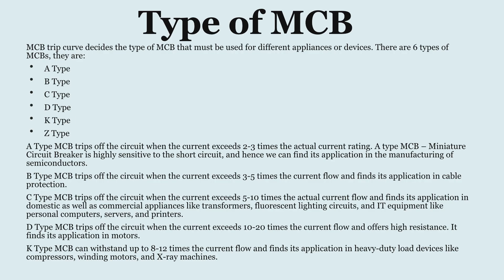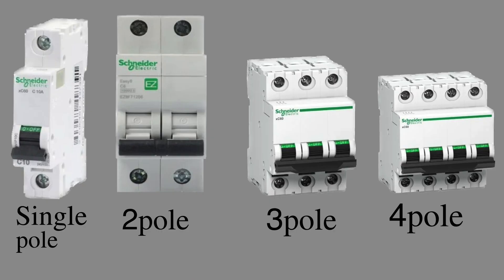There are six types of MCB: Type A, B, C, D, K, and Z. Type A MCB trips when the current exceeds two to three times the actual current rating. Type B trips at three to five times and is used basically for cable protection. Type C trips at five to ten times and is mostly used for transformers, lighting, cable, IT equipment, personal computers, etc. Type D MCB can trip at ten to twenty times the actual current.